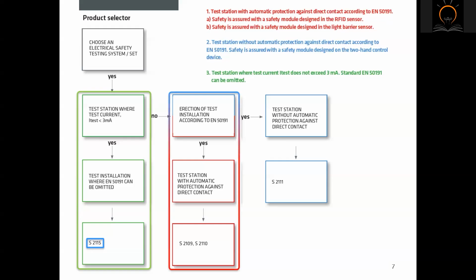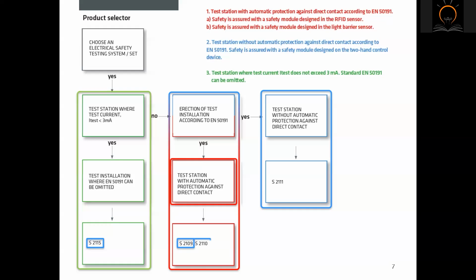If we can't avoid following the requirements from EN 50191, there are still two main options available: a test station with automatic protection against direct contact and a test station without automatic protection against direct contact. In the field of test stations with automatic protection against direct contact, Metrel has prepared two solutions. One where safety is assured with a safety module designed for the RFID sensor. It is S2109. And the one where the safety is assured with a safety module designed for the light barrier sensor. This one is S2110. In the field of test stations without automatic protection against direct contact, Metrel has prepared a solution with the two-hand control device, and this is S2111.